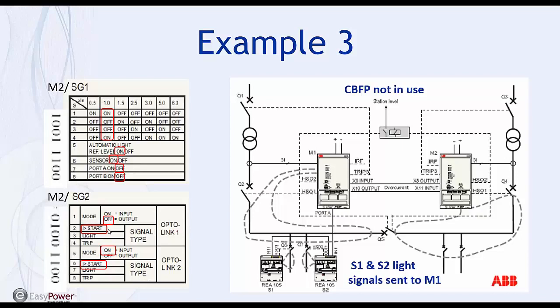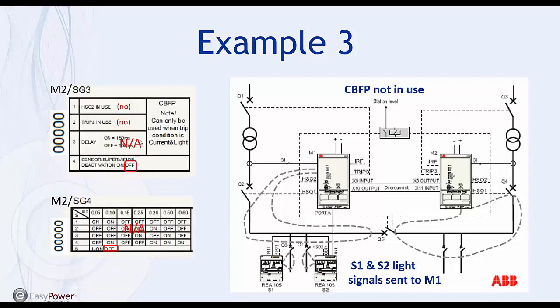So when you see that fault detector level, then the REA 105 is going to receive that information, and as long as there's light detection, it'll trip its dedicated output and provide the selectivity. So here's the breaker failure, we're not going to use that on M2 either. And we'll have the sensor supervision. We're not going to use the ground.